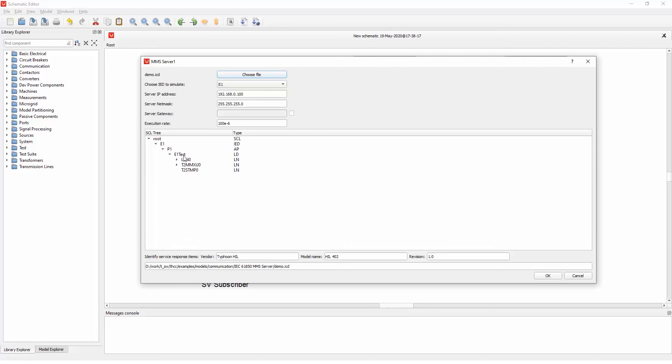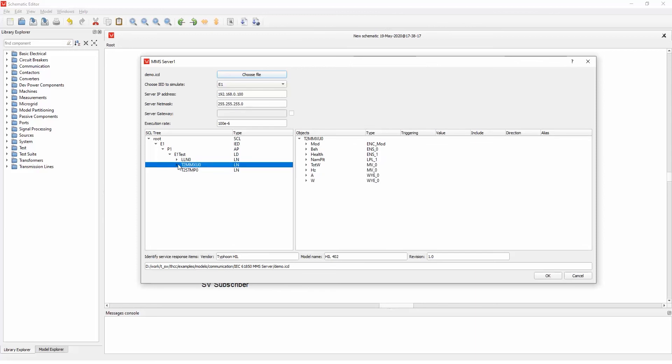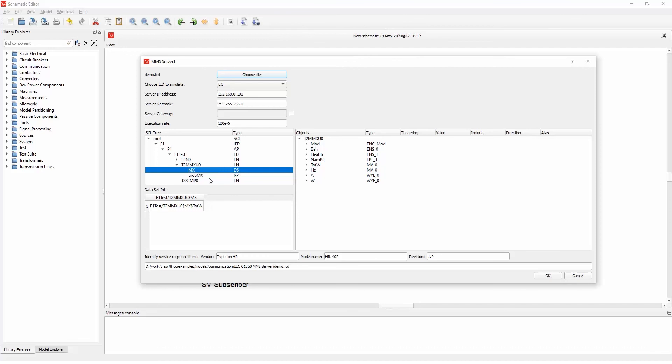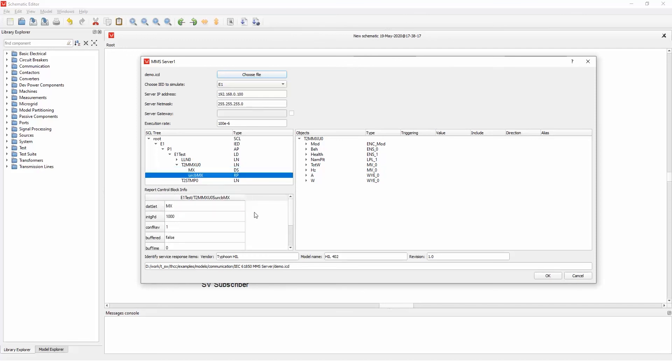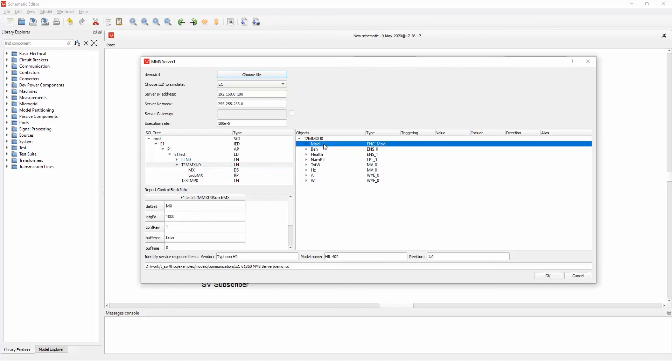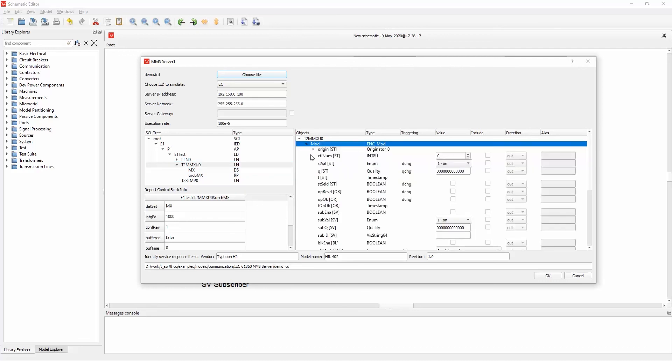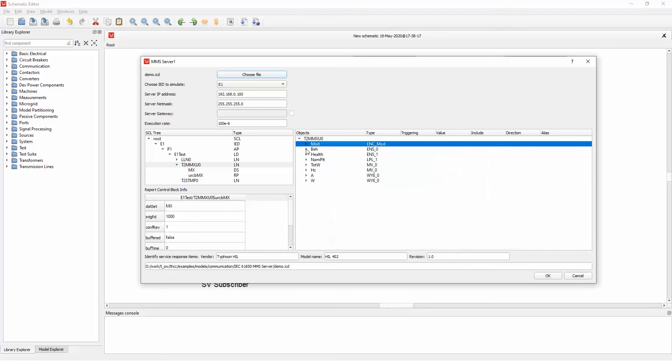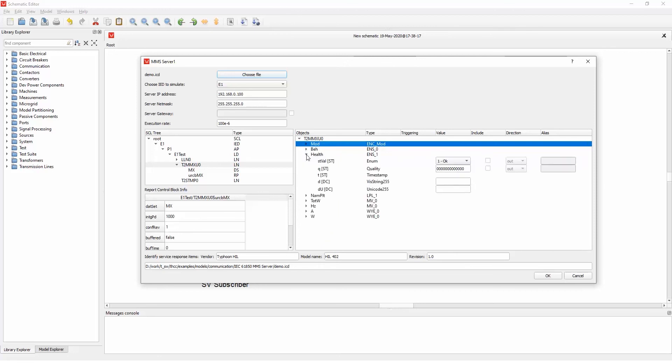And you can see that there is an E1 test, the logical node zero, and other logical nodes that you can select and see the data sets, the reporting block, and so on. If you select the logical node and inside the logical node, you can see all the fields for mode, behavior, health, and so on.